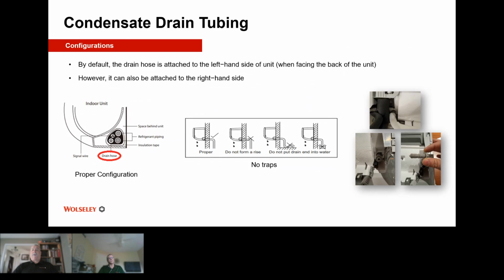And just to leave everybody here, condensate from high wall units is under no pressure at all. It is strictly falling off the coil into a pan and being collected, and once it collects enough, it will exit out of the left port if that's where it's been attached, or it will exit out the right port. But it is under no pressure whatsoever. As you can see here, there are 4 things that we want to make sure of. Number 1, that we have a proper condensate drain coming out of the back: no kinks, no rises, and that it's not put into a water pan or a pump where the end is submerged. We want to keep it so that it does not get waterlocked, so that gravity will do its job and it will keep flowing out.